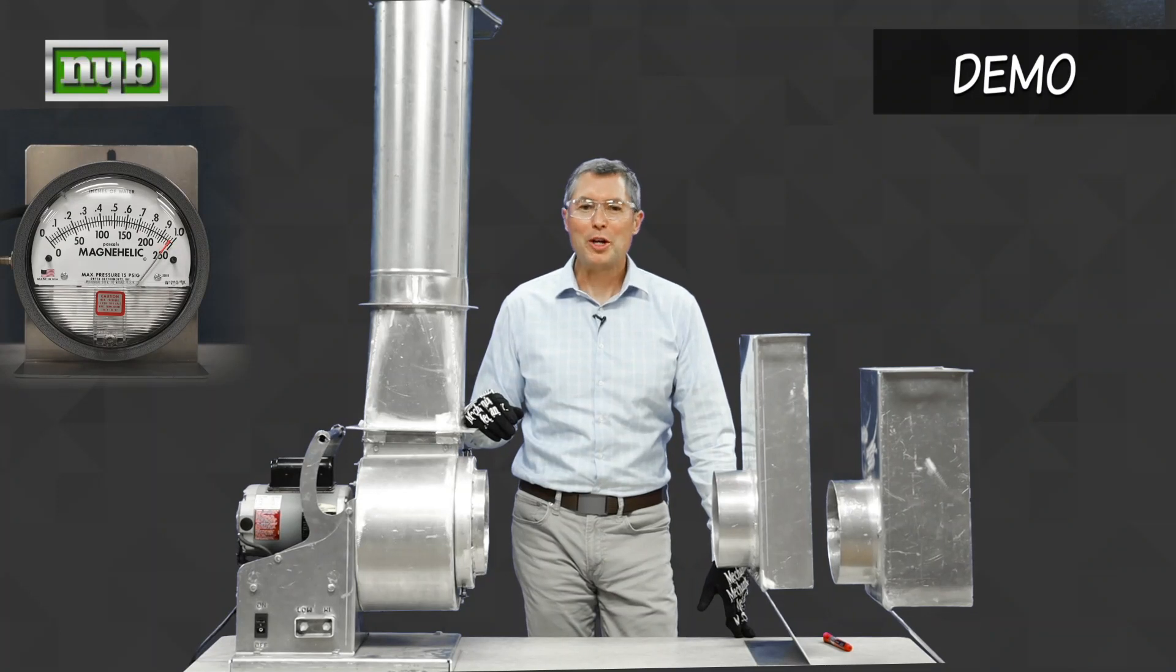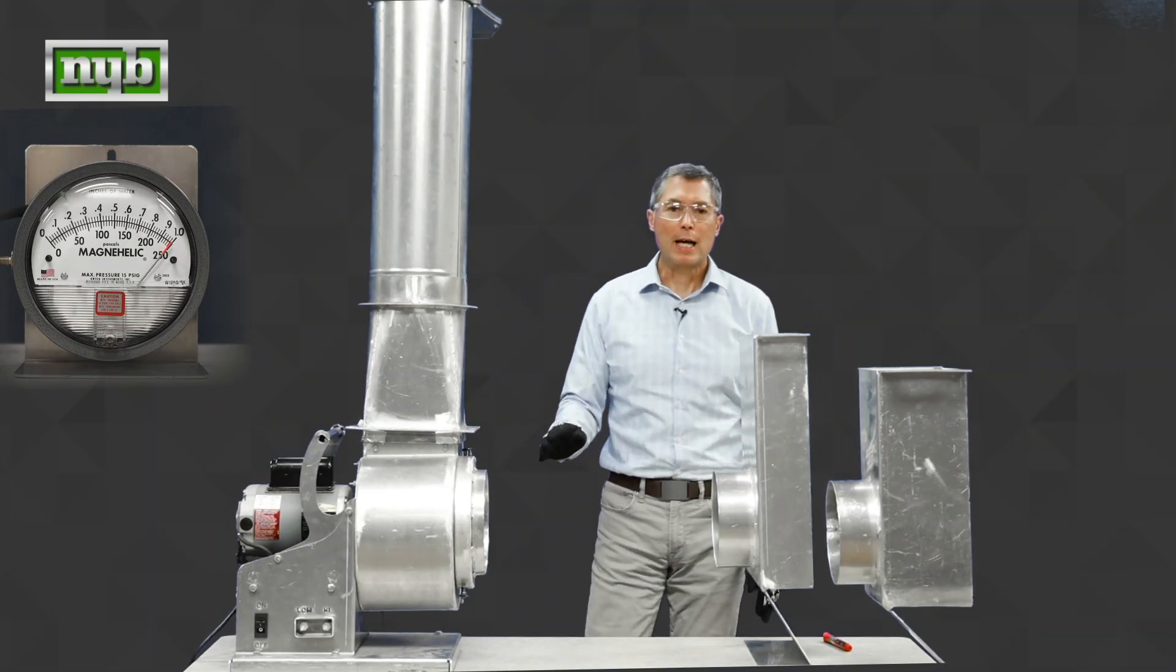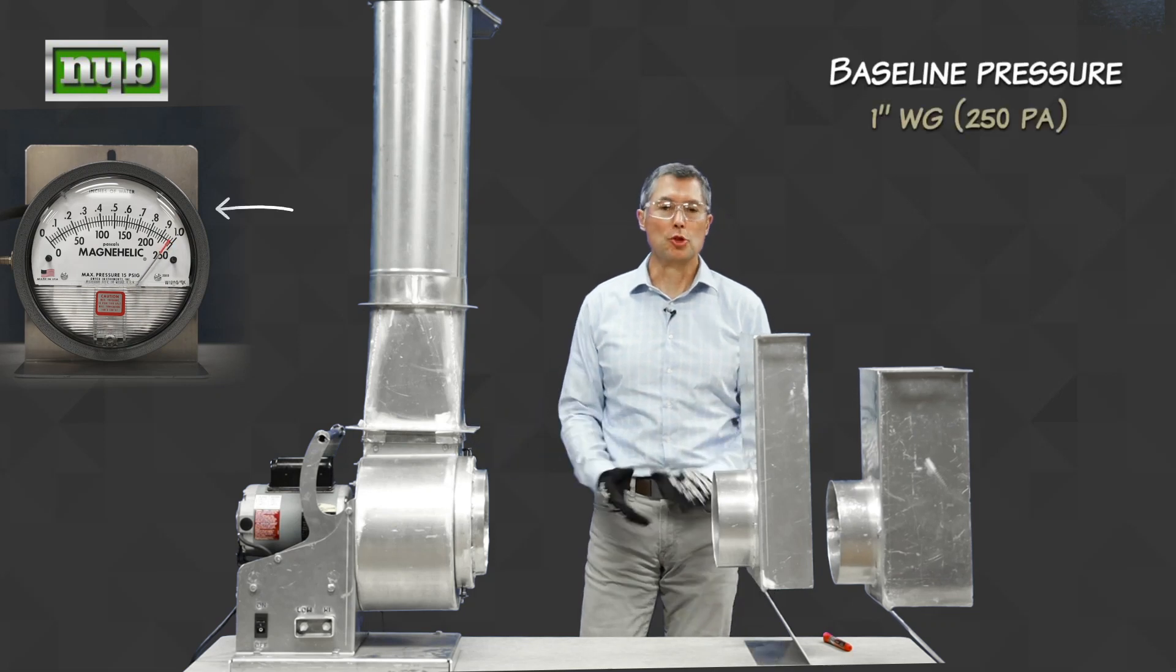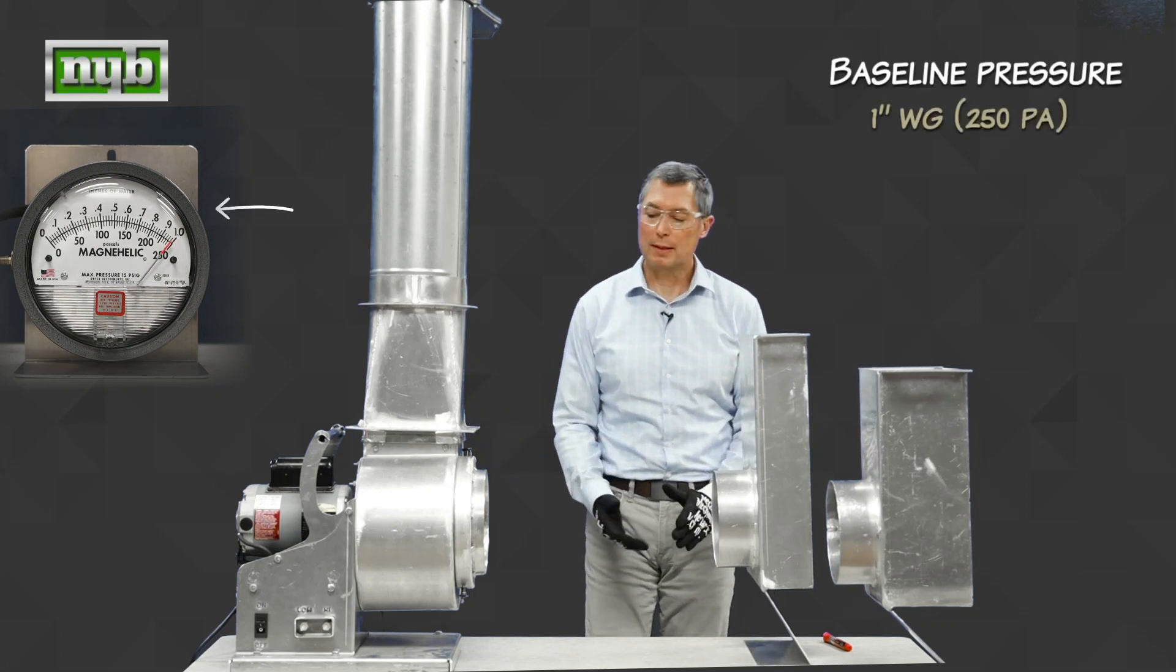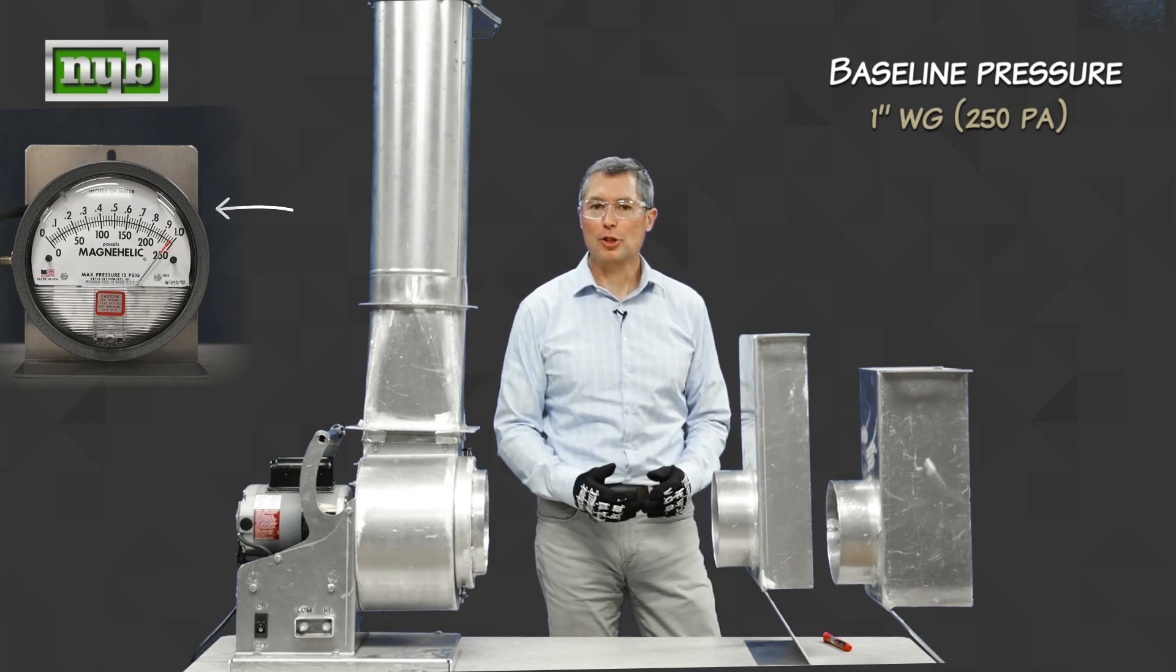Let's move on to the demo, the reason why you're actually watching this video. As you can see, fan is on. Baseline number is one inch of water gauge or 250 Pascal, open inlet. Let's see what happens when we add an inlet box to the fan.